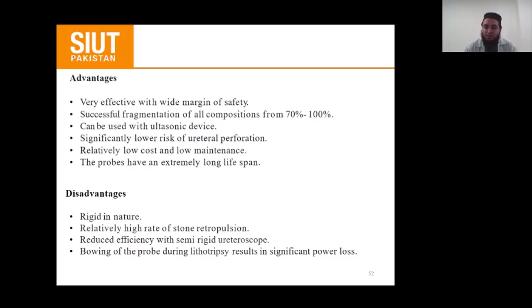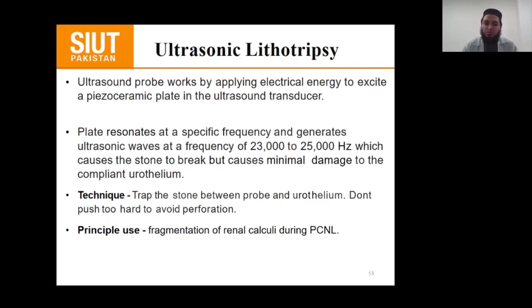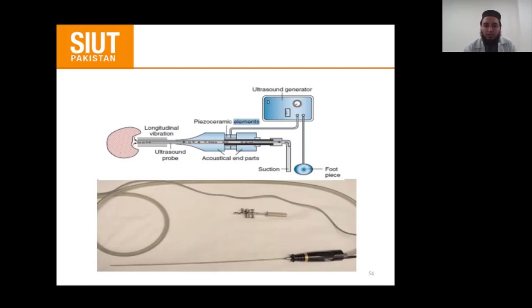Ultrasonic lithotripsy. The ultrasound probe works by applying electrical energy to excite a piezo-ceramic plate in the ultrasound transducer. The plate resonates at a specific frequency and generates ultrasonic waves at a frequency of 23,000 to 25,000 Hz, which causes the stone to break but causes minimal damage to the compliant urothelium. The technique is that we have to trap the stone between the probe and the urothelium, and we should not push too hard to avoid perforation. Its principal use is in the fragmentation of renal calculi during PCNL. You can see the ultrasonic lithotripter with piezoceramic elements and its longitudinal vibration.